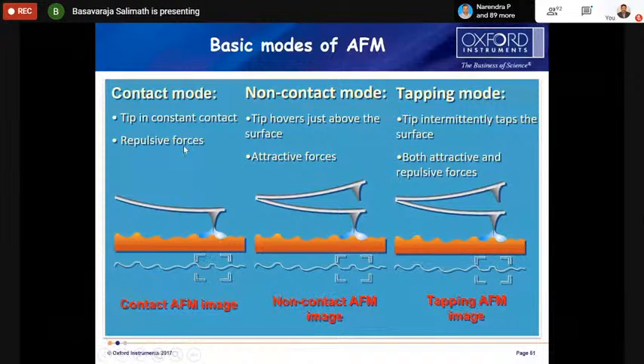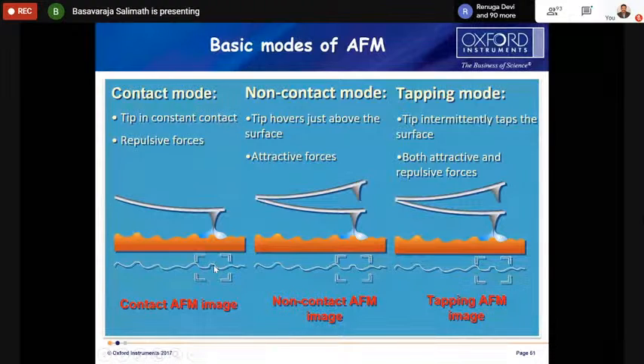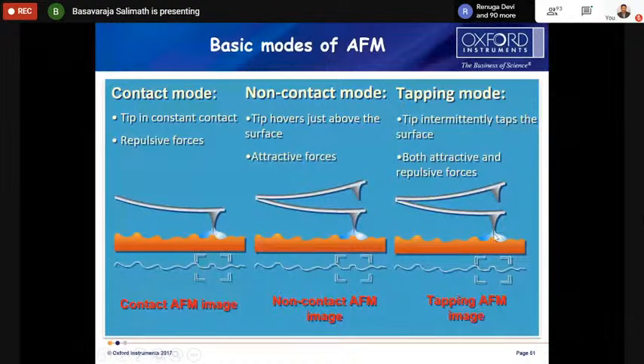Contact mode works in the repulsive force region, and as it is touching the sample, if we have some small water layer on the sample, as we are doing AFM in ambient conditions, sometimes because of humidity a very small amount of water layer may be there on the sample. But in contact mode, as it is touching the sample, it will go inside this water layer and scan the surface, so you will get the correct surface morphology. In the case of tapping mode also, it is oscillating and tapping the surface, so here also it goes inside the water layer and gives us the correct image.